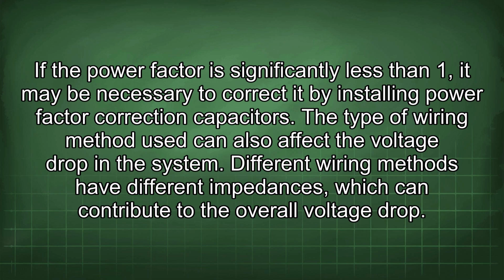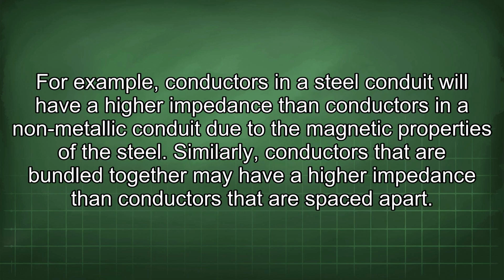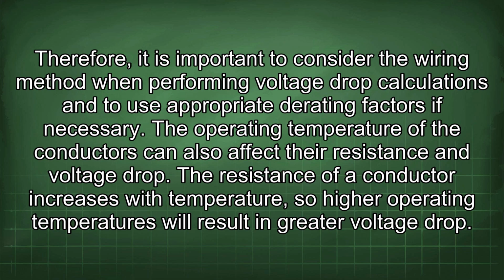Different wiring methods have different impedances, which can contribute to the overall voltage drop. For example, conductors in a steel conduit will have a higher impedance than conductors in a non-metallic conduit due to the magnetic properties of the steel. Similarly, conductors that are bundled together may have a higher impedance than conductors that are spaced apart. Therefore, it is important to consider the wiring method when performing voltage drop calculations and to use appropriate derating factors if necessary. The operating temperature of the conductors can also affect their resistance and voltage drop. The resistance of a conductor increases with temperature, so higher operating temperatures will result in greater voltage drop.